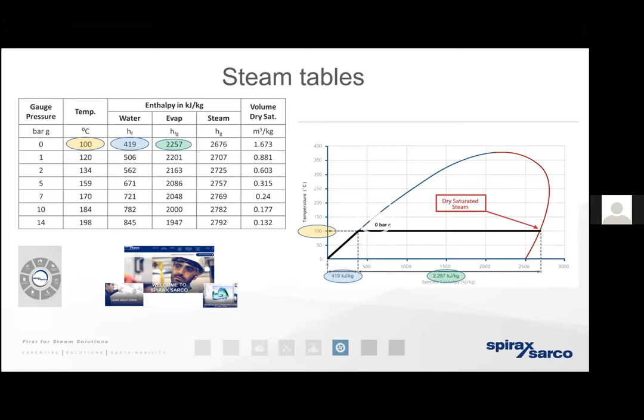Looking at the final column in the chart, that one kilogram of steam now occupies a much larger volume because it's a gas — 1.673 cubic metres. Once fully evaporated, that kilogram of steam has a total energy content of 2,676 kilojoules. The interesting thing is when the steam condenses, whether in the distributing pipework or at the heat exchanger, it's the enthalpy of evaporation — the latent heat — that is released across the thermal barrier into the process.